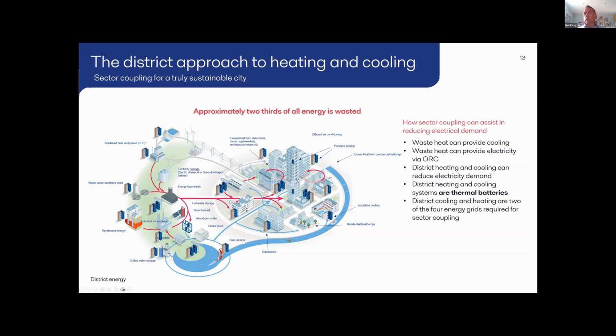The district systems can also be thought of as thermal storage. The pipes in the ground are thermal stores, and that allows you to take from that thermal store when there is either no renewables or when there's some lower carbon sources that can be utilized. And the effect of that thermal store, you can charge it at times when you have the energy, and when the energy is non-existent or less than required, you can then take from the thermal store. So those pipes in the ground allow you to peak shave the peaks of demand. And the more you smooth the demand profile, the more renewable energy you can integrate into that.